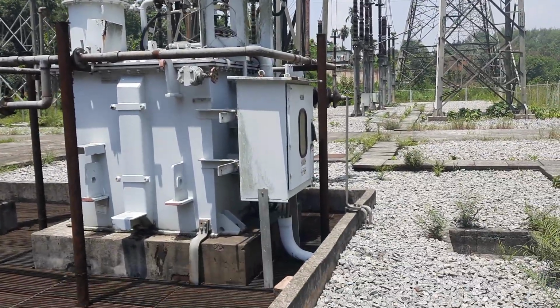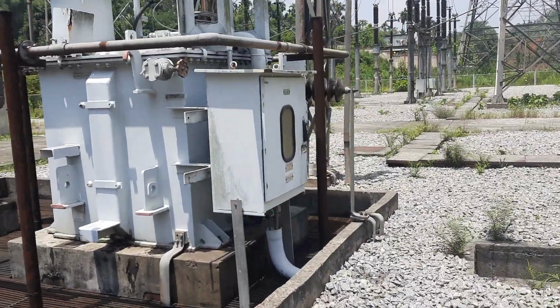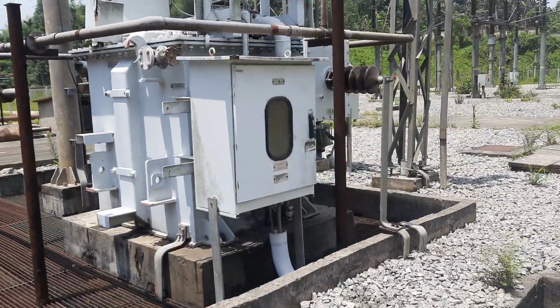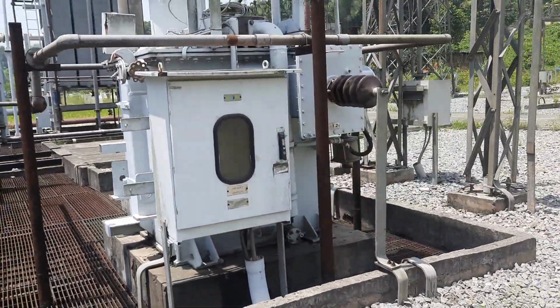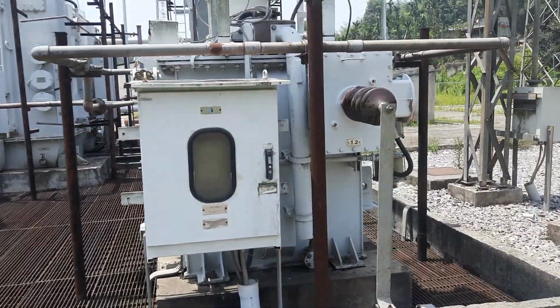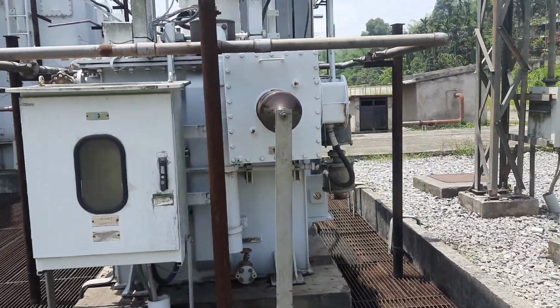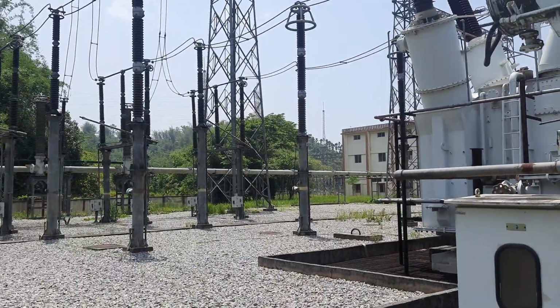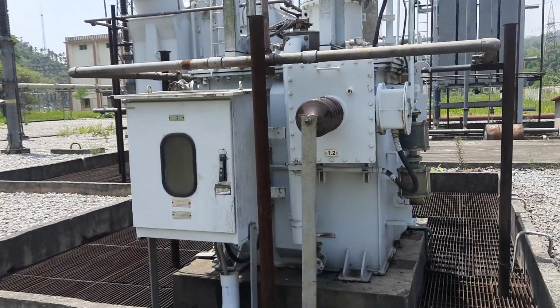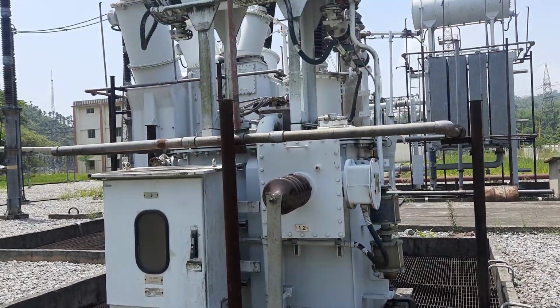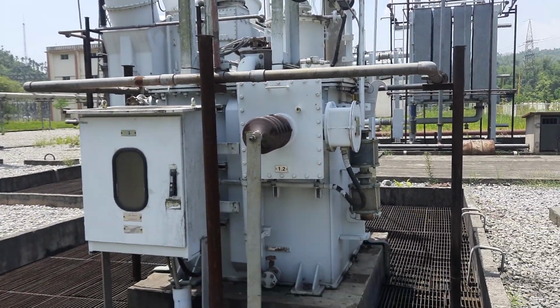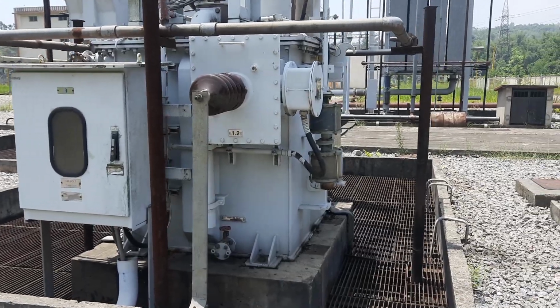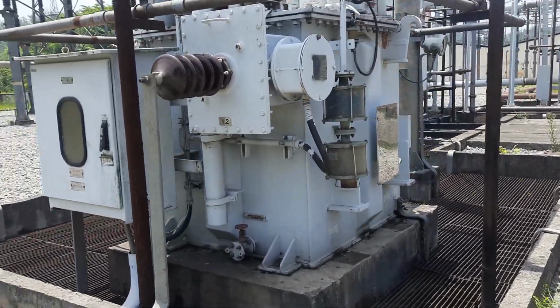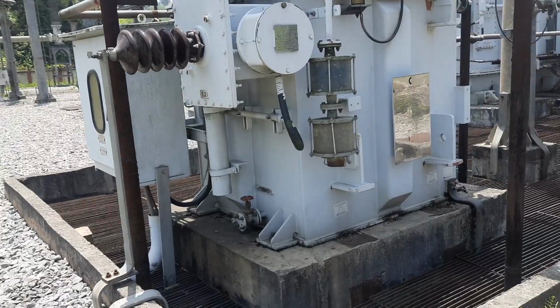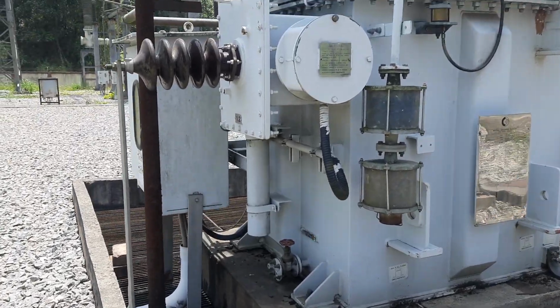What is the purpose of NGR? The purpose of this is to help in reducing the magnitude of fault current. If the line that we are talking about gets an arc fault or something, then to limit the arc fault current we are putting this neutral grounding reactor. So you can see the placement is like this.